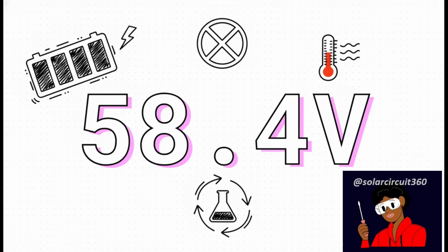Let's look at the baseline math. For a standard 16-cell series LiFePO4 pack, the maximum charging voltage is calculated by multiplying 16 cells by 3.65 volts. That gives us a hard, non-negotiable limit of exactly 58.4 volts. This is exactly why a lot of 48-volt chargers use 58.4 as their absolute absorption ceiling.